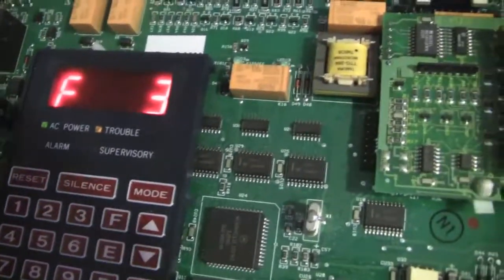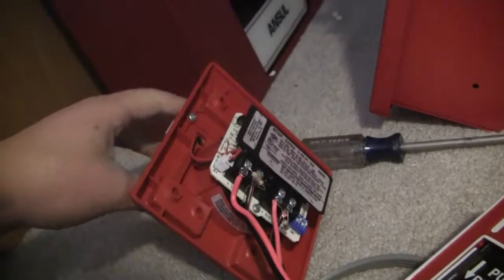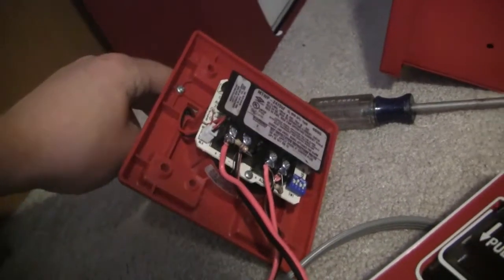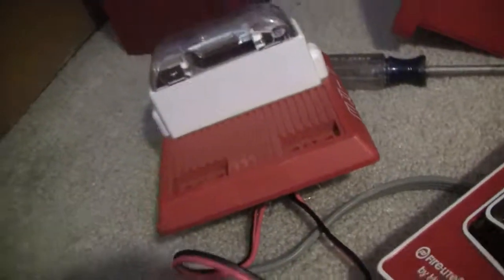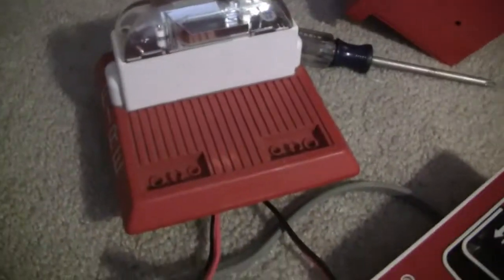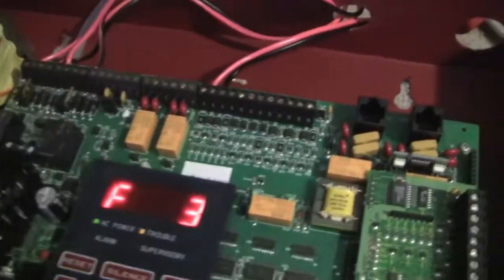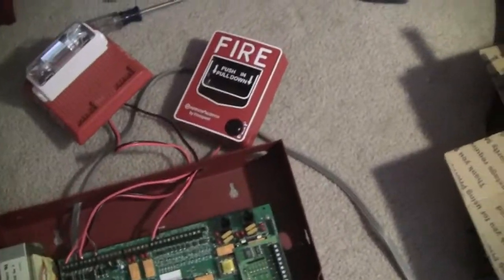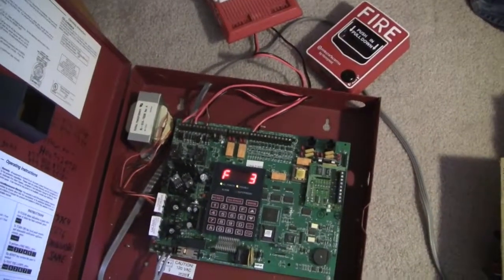What I have set up to test this system is a FireLite BG-12 and a Wheelock MTWP 2475W outdoor horn strobe, 180 candela. I have that set to bell, and I have the panel coding it to March time. So let's just do a quick test, and then I will explain about this panel a bit more.